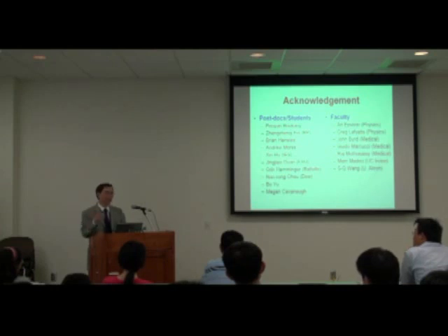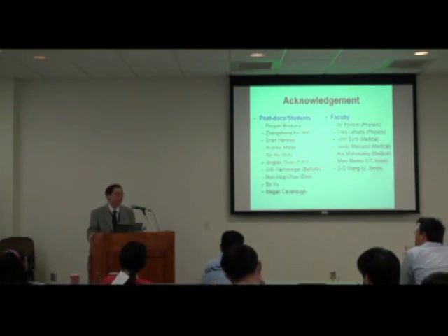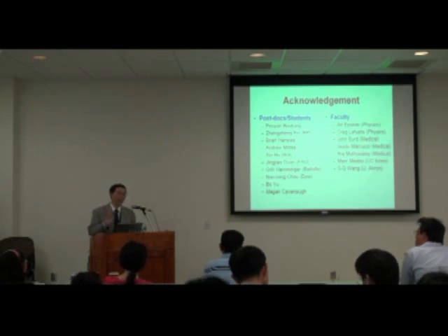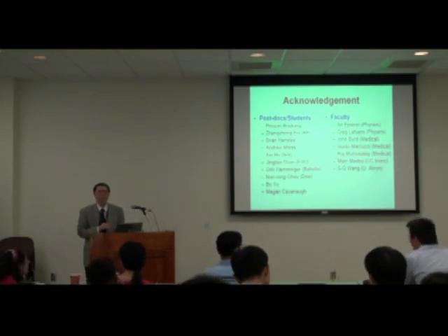There are a lot of people who put a heating element. My view is that the analyzer can be expensive, because you don't throw it away. But the CD is disposable, so I want to make it as cheap as possible. If you put a heating element on that, you have to consider the cost. In principle, yes, you can put in the function. The question is that we have to make it very, very low cost. My philosophy is to make it simple. But to answer your question, yes, you can put in a local heating element. It has been done by many other researchers. Okay, thank you.